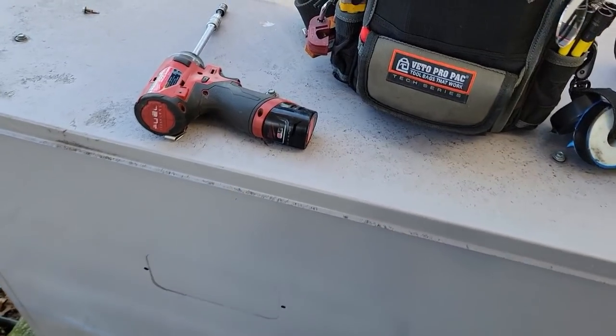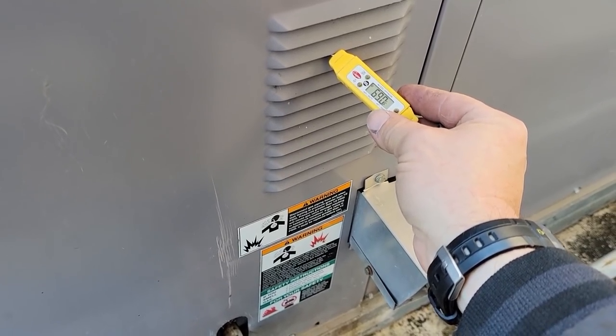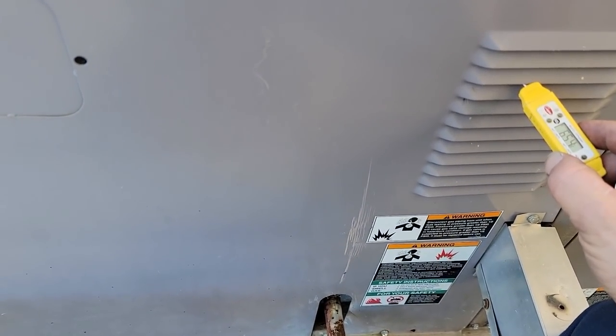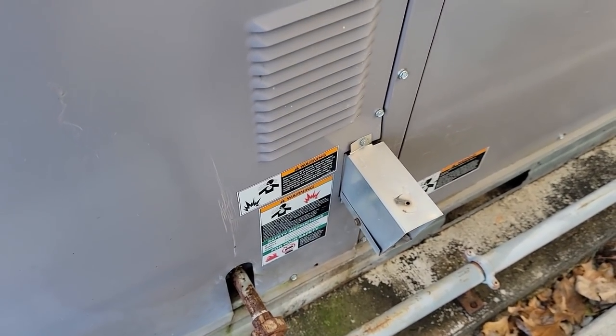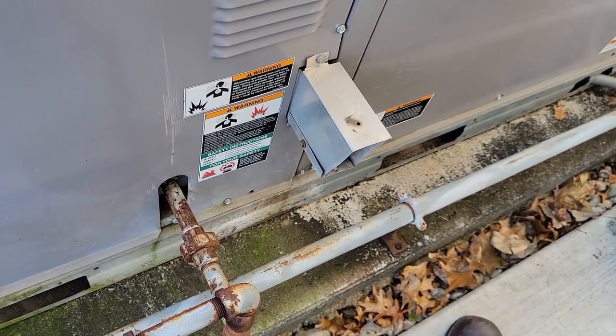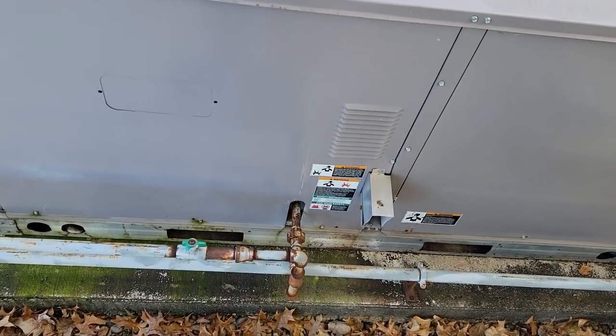Alright, it's running. Let's see what kind of temperatures we get in here — I highly doubt it's anything crazy high. We're already dropping down to 68. Let's try blocking it off a little bit, see if that makes any difference. Yeah, it's going up a little bit. I held that block right up there and it didn't rise much at all. I suppose it could recirculate if the wind was blowing just right, but I don't think that's the case. The sensor's getting weak, so we'll just get a new one on it. Filters are fine, belt's tight. I think they're due for maintenance before long. We're going to wrap this one up.